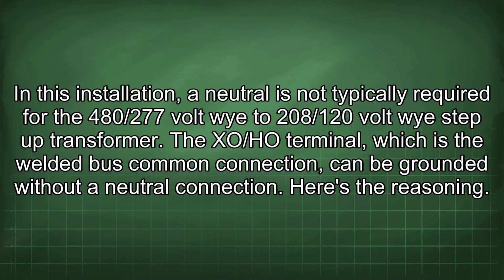In this installation, a neutral is not typically required for the 480/277 volt Y to 208/120 volt Y step-up transformer. The XO/HO terminal, which is the welded bus common connection, can be grounded without a neutral connection.